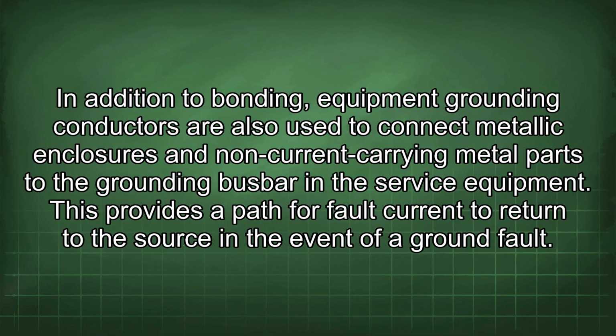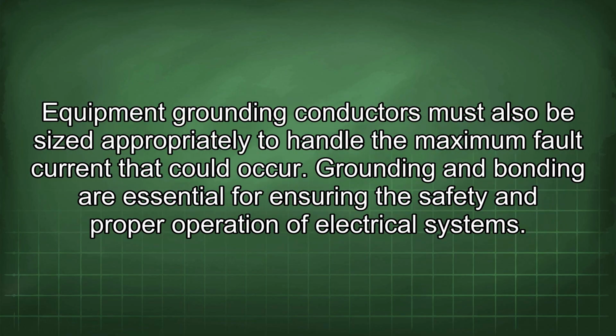Bonding jumpers must be sized appropriately to handle the maximum fault current that could occur. In addition to bonding, equipment grounding conductors are also used to connect metallic enclosures and non-current carrying metal parts to the grounding busbar in the service equipment. This provides a path for fault current to return to the source in the event of a ground fault. Equipment grounding conductors must also be sized appropriately to handle the maximum fault current that could occur.